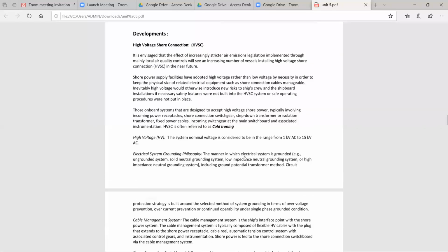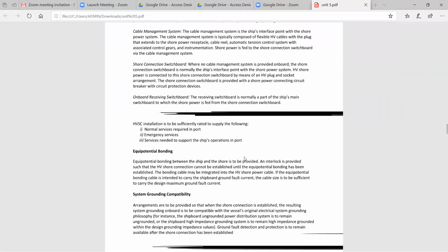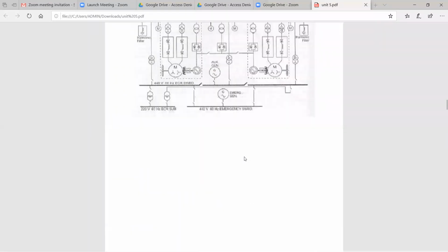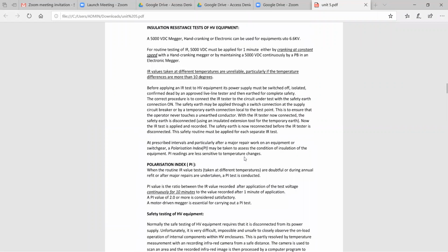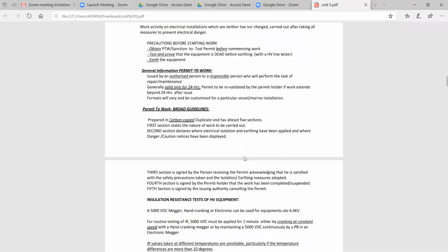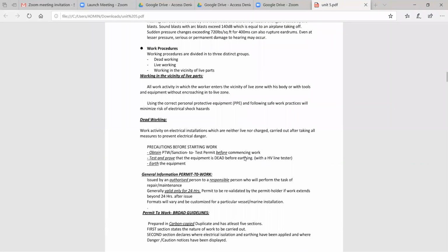Recorded high voltage system. So if we consider the first one on the work permit, the work permit has to be classified for a certain category. The first category can be considered for a risk factor. That means dead working, live working, working in vicinity of live parts. Number one is dead working. Number two is live working. Number three is work in vicinity of live parts. So your first one is working in vicinity of live parts.